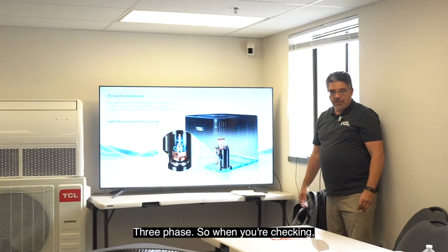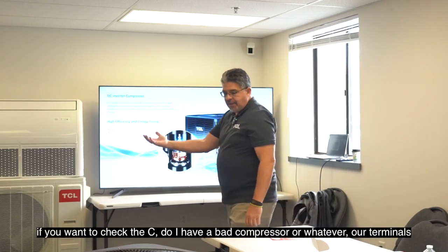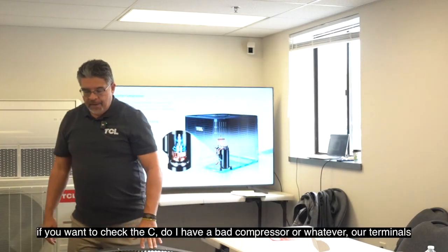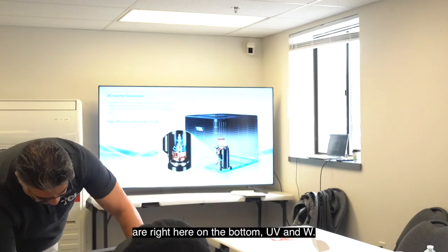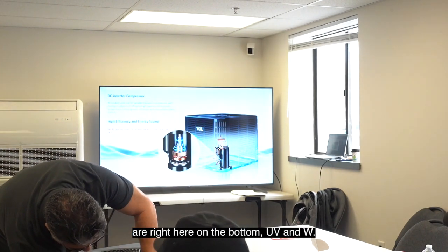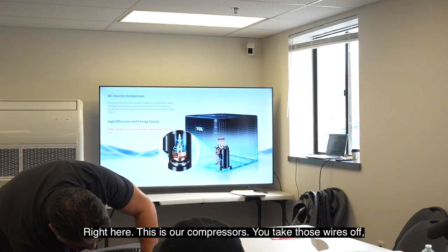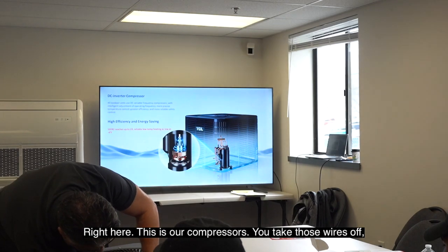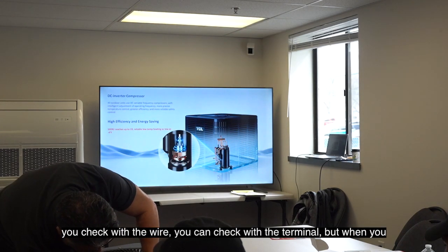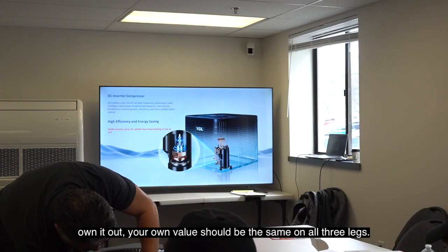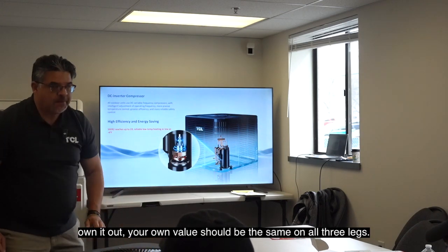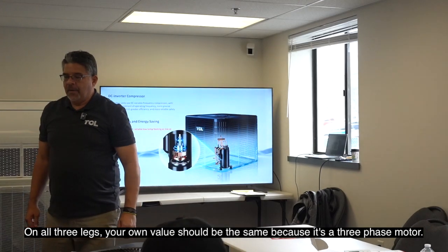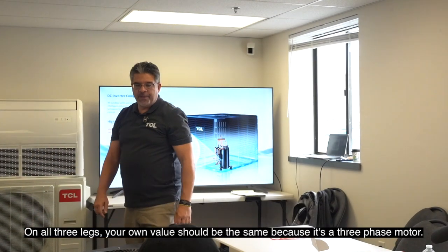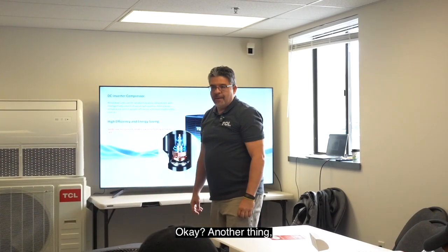3-phase. So when you're checking, if you want to see, do I have a bad compressor or whatever, our terminals are right here on the bottom, U, V, and W. This is our compressor. You take those wires off, you check with the wire, you can check it at the terminal, but when you ohm it out, your ohm value should be the same on all 3 legs. On all 3 legs, your ohm value should be the same because it's a 3-phase motor.